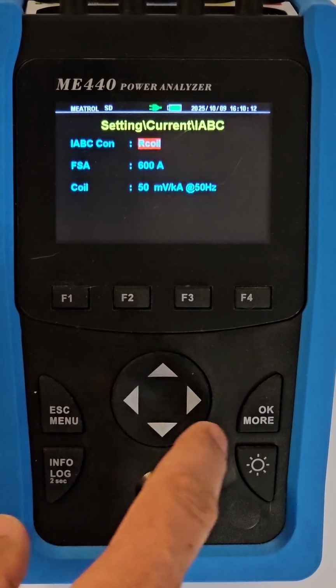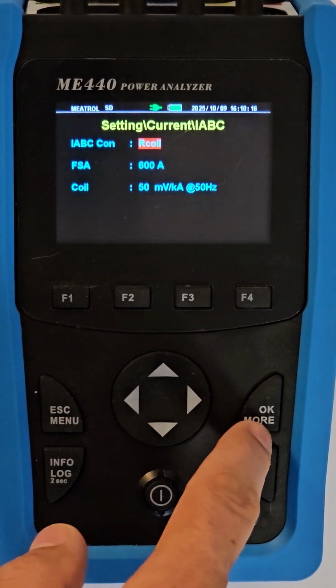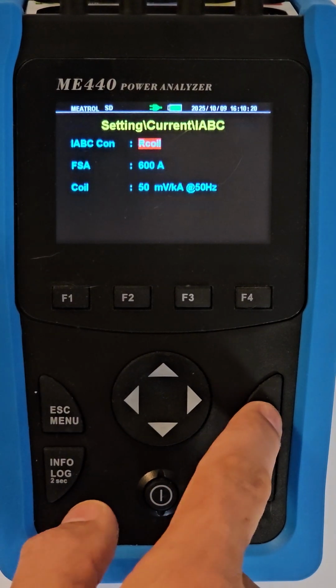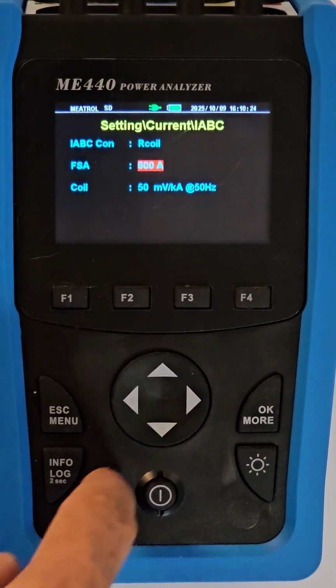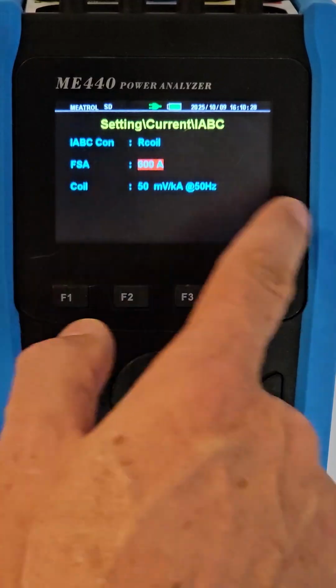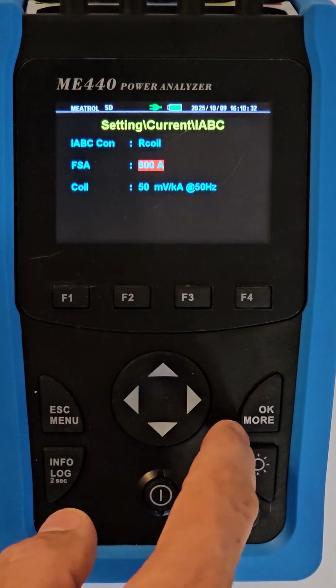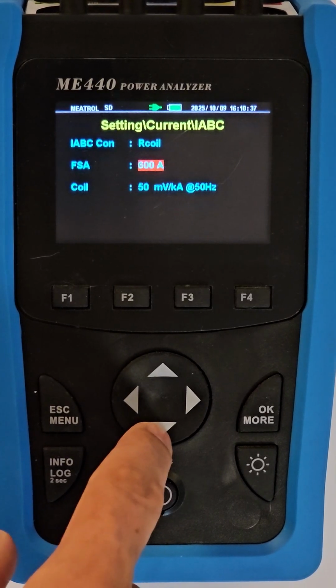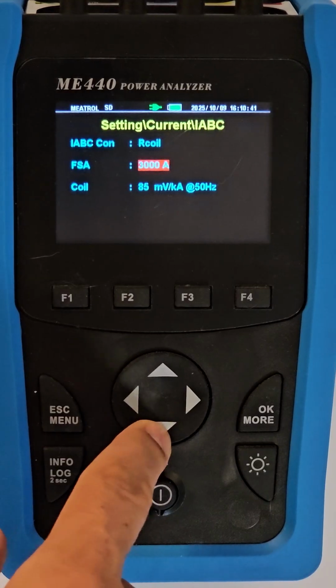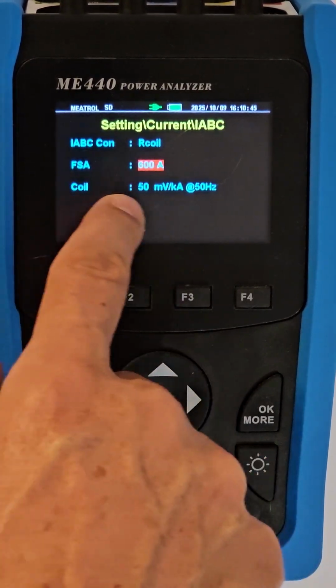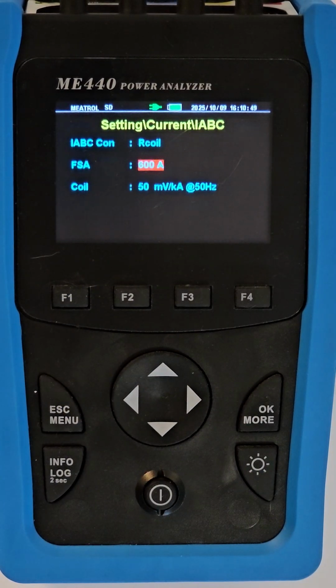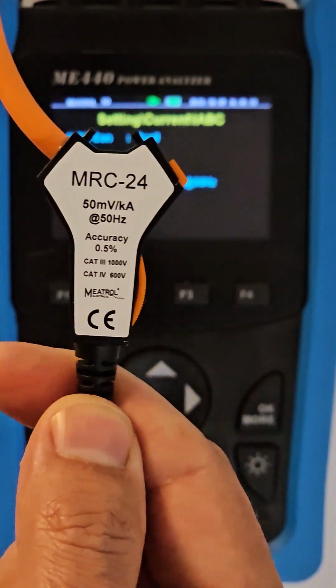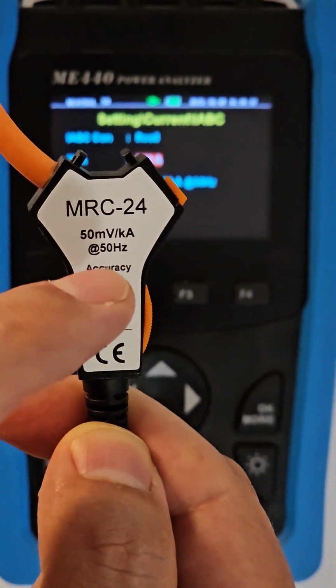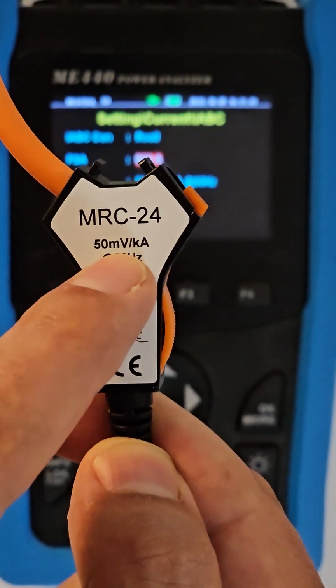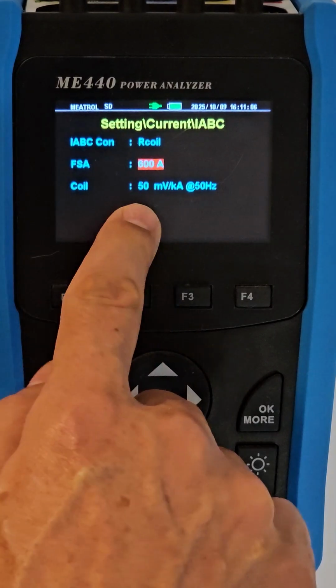So if we go into Rogowski coil, you'll see the first setting is FSA. That stands for full scale amps. So that's basically the range that the meter can measure. That can be changed to either 600, 6000 or 3000. Also it's important to make sure that the range is set correctly for the coils you're using. So for the ME440 coils, that goes up to I think 600 amps. You'll see there's a sensitivity of 50 millivolts per kiloampere. So it's important to match that with the setting here, which is 50 millivolts per kiloampere.